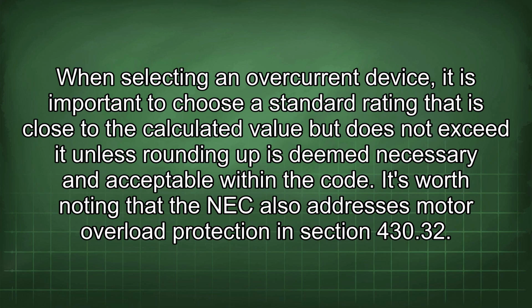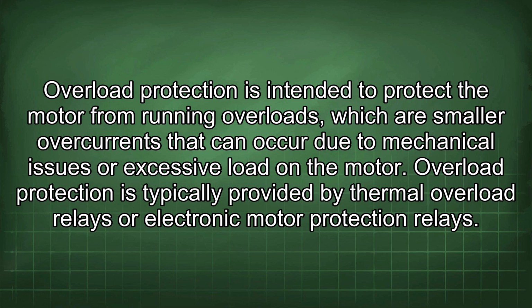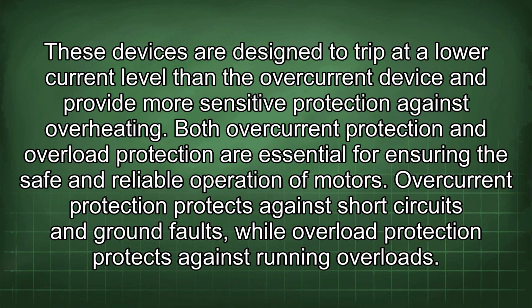It's worth noting that the NEC also addresses motor overload protection in section 430.32. Overload protection is intended to protect the motor from running overloads, which are smaller overcurrents that can occur due to mechanical issues or excessive load on the motor. Overload protection is typically provided by thermal overload relays or electronic motor protection relays. These devices are designed to trip at a lower current level than the overcurrent device and provide more sensitive protection against overheating. Both overcurrent protection and overload protection are essential for ensuring the safe and reliable operation of motors. Overcurrent protection protects against short circuits and ground faults, while overload protection protects against running overloads.